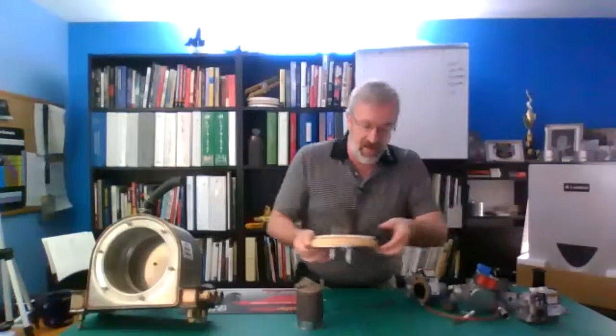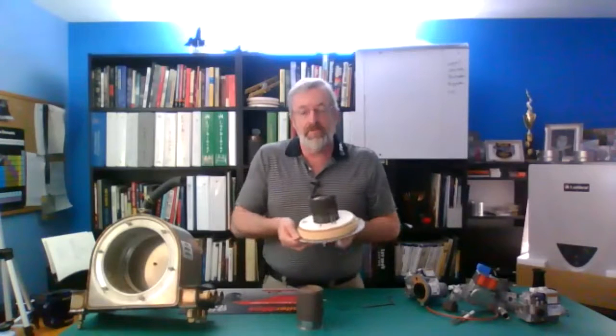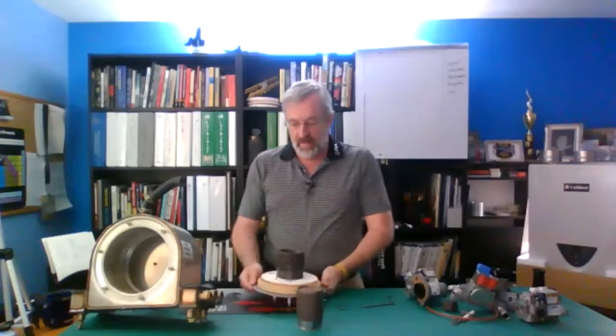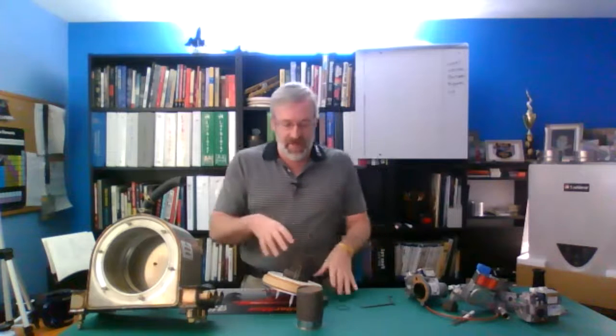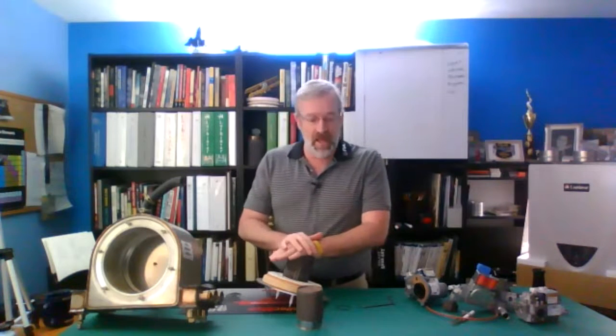Now, when I'm in this style here, what I'm going to do on this one will be to remove my igniter and flame sensor. My refractory is going to lift up. And at that point in time, I'm going to be at my burner bolts. Take your burner bolts, pull the burner off, do that. Now in this model, when I'm in a fire tube style, I will need to replace the burner gasket. When I'm in that style, there actually isn't generally a burner gasket that I'm replacing on that. It kind of tucks in the other way, a little bit different design on those. But on this one, I'm always going to replace that burner gasket if I take it apart.